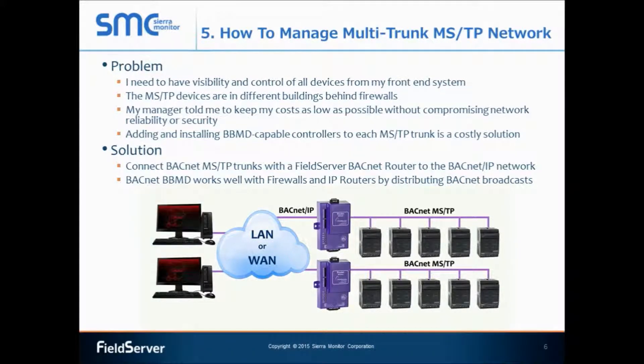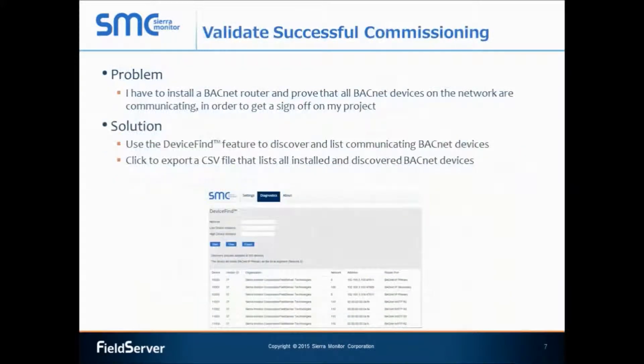To successfully validate that all devices have been connected to the FieldServer BACnet router, there is a unique feature called DeviceFind. DeviceFind enables all devices connected to the BACnet router to be seen through the diagnostics page built into the router. Once all BACnet devices connected to the router have been seen, the list of connected devices can be exported via CSV file, which can be kept as verification that all devices have been commissioned to the BACnet router.